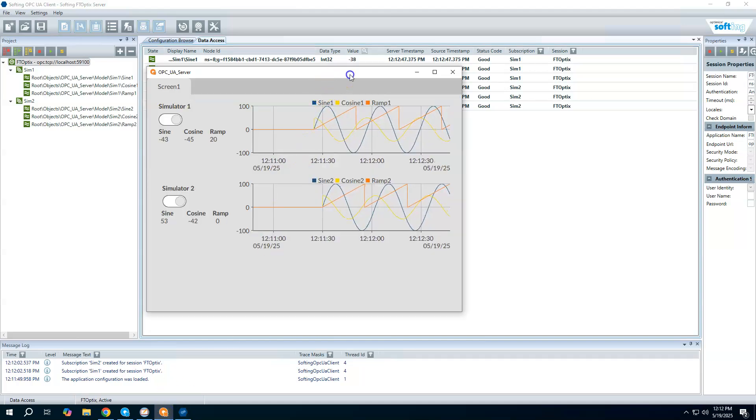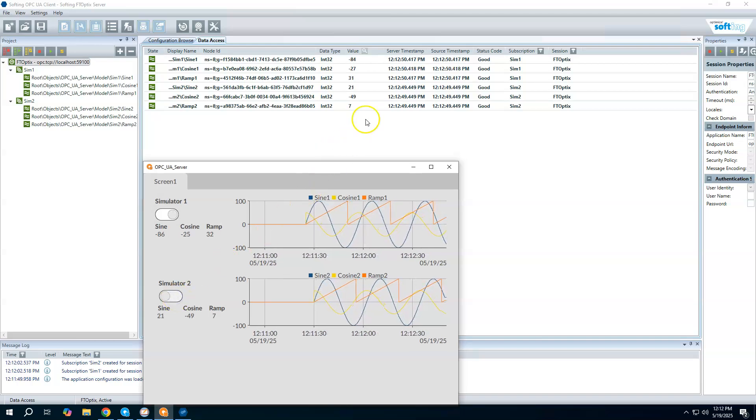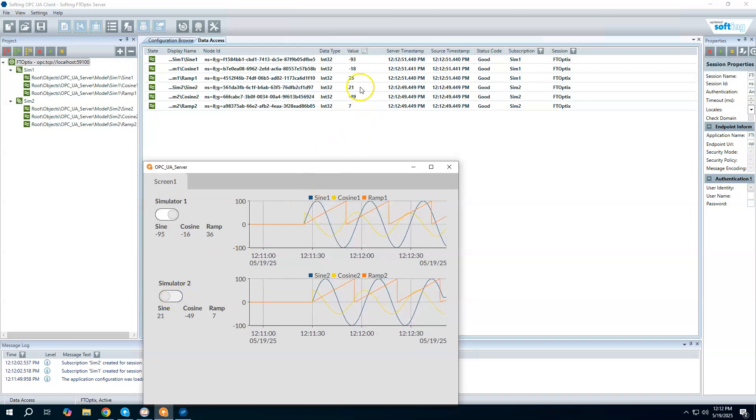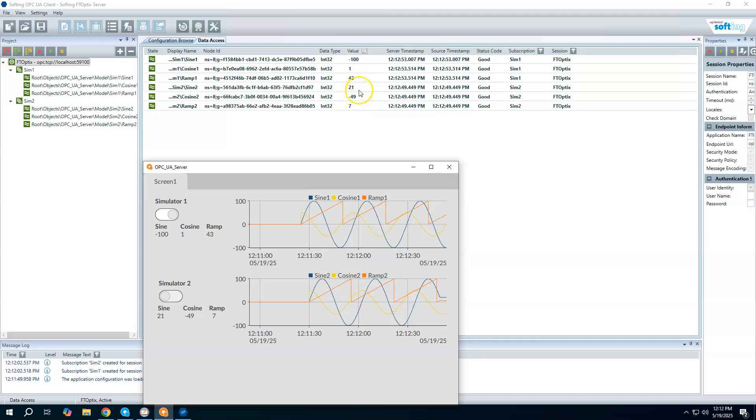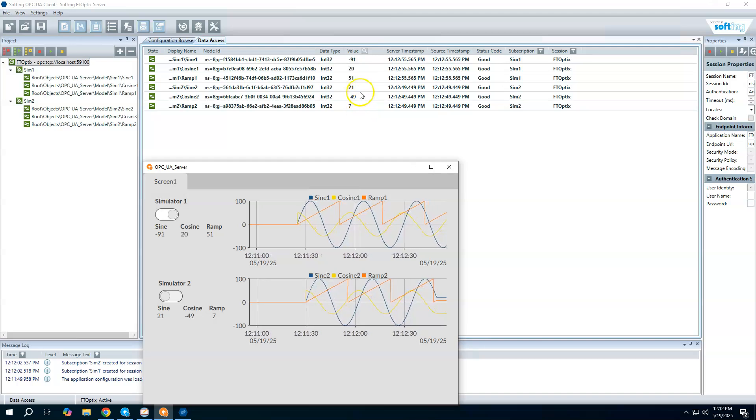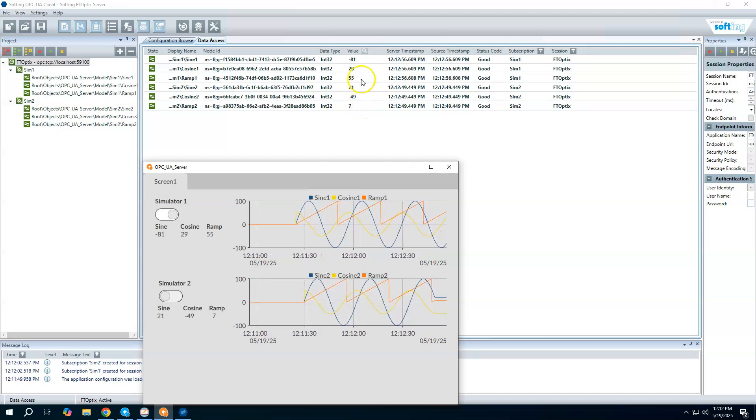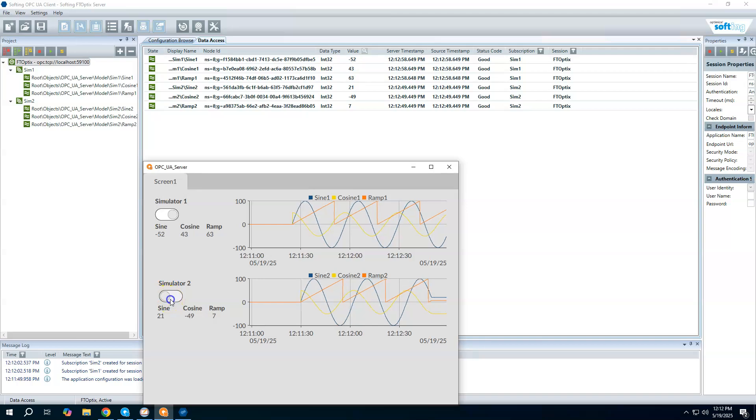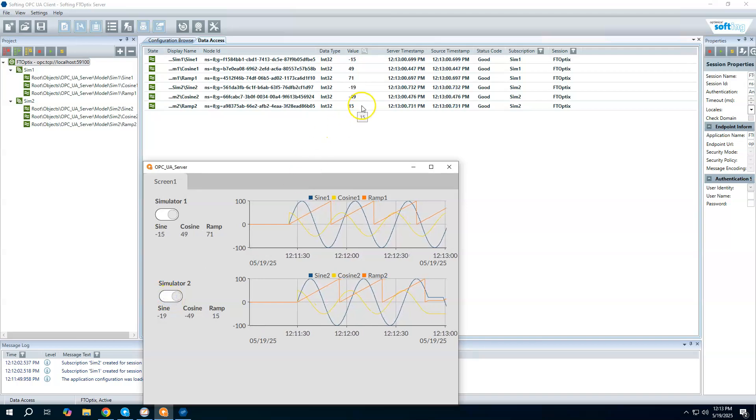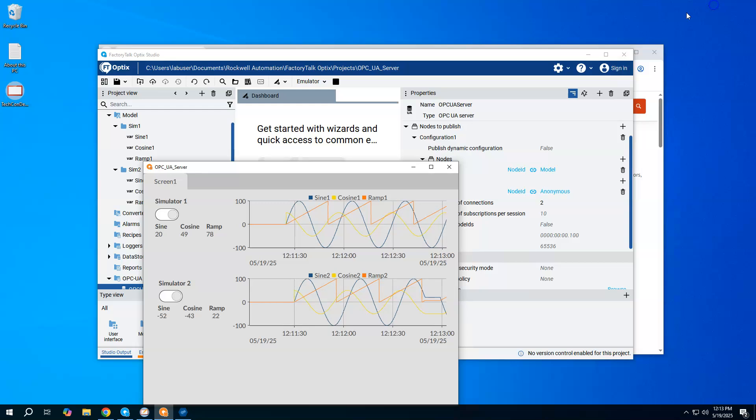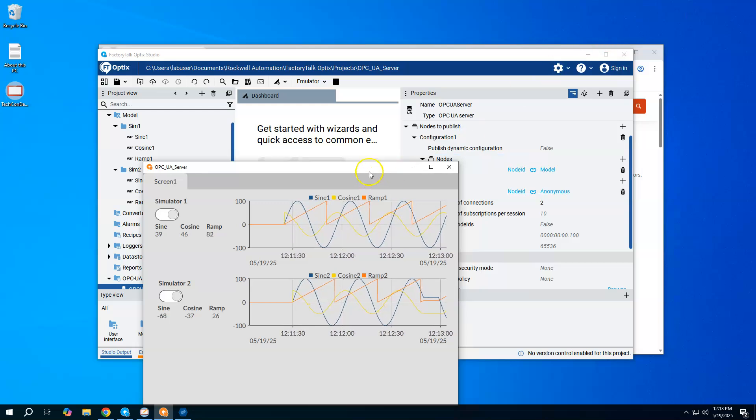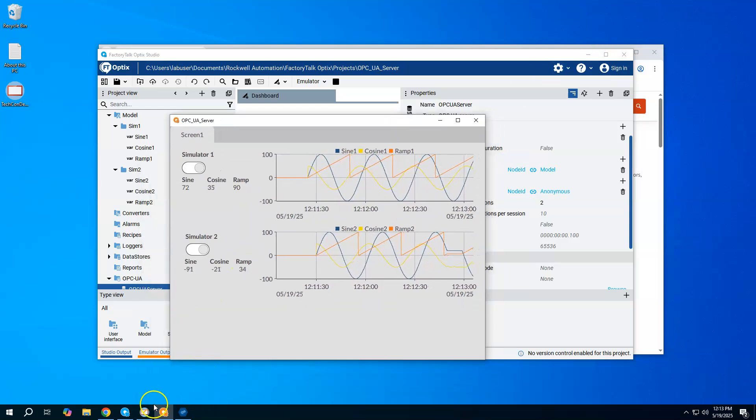The point of this was just to show that here's our sine one, cosine one, ramp one, and then simulator two values as well. We are getting data updating from the OPC UA server. Just to show, if I were to stop simulator two, we see here that simulator two data is basically now frozen, not updating, where simulator one still is. We'll go ahead and start it back up again. Just proving that we can make that connection.